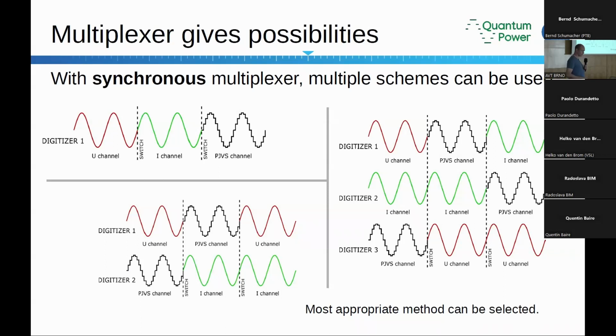Yeah, colleagues said it already that when we got a multiplexer that is synchronous, we can make multiple setups or multiplexing schemes that can be useful for different scenarios. And for the power, there are two very important things. For example, we can measure power in this system. First, we will use one digitizer to measure a voltage. Then we will switch the multiplexer and use the digitizer to measure the current. And then we can switch the multiplexer and we will measure the Josephson, and this Josephson will be used to calibrate the digitizer itself. And from the voltage and current and amplitudes and phases, we can calculate the power.